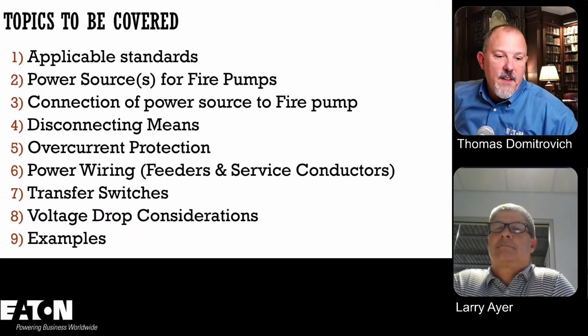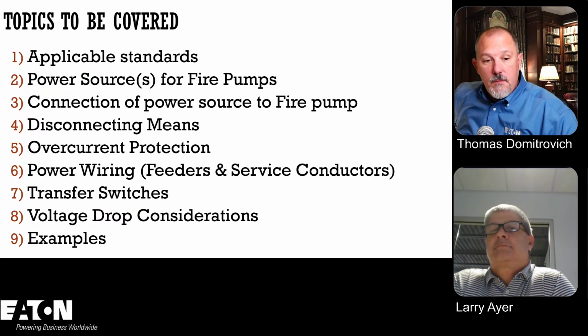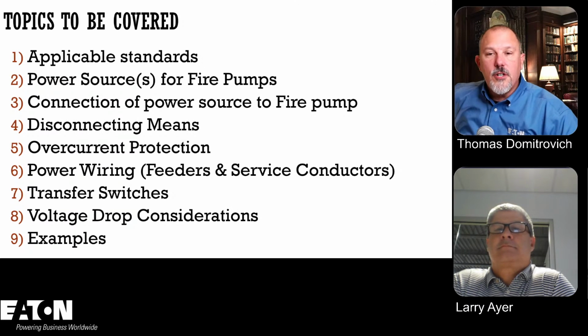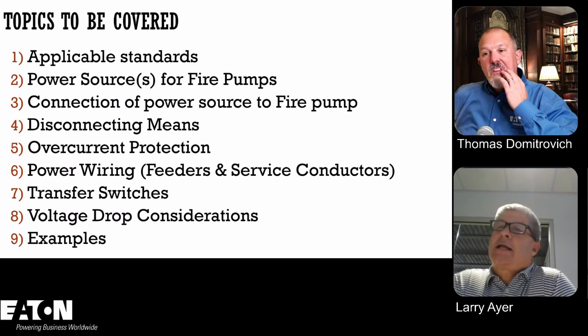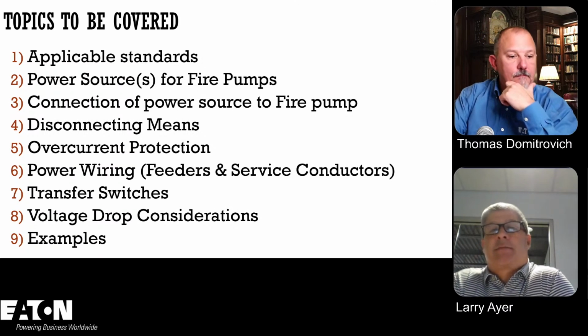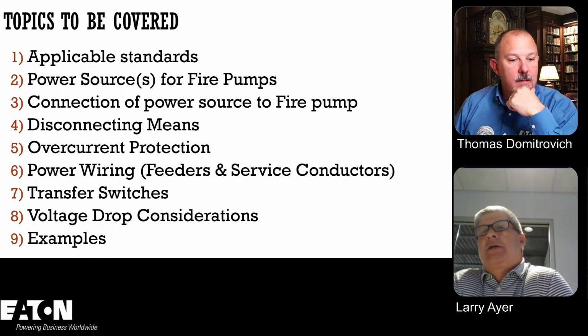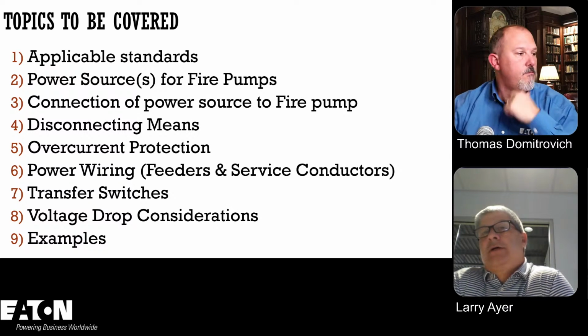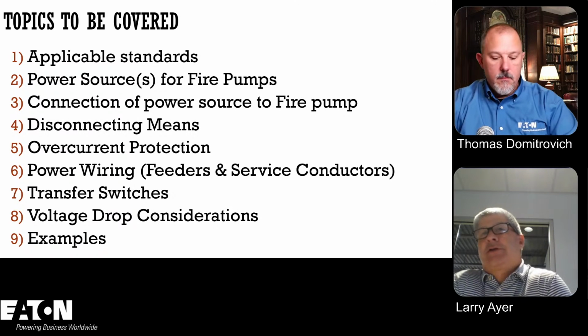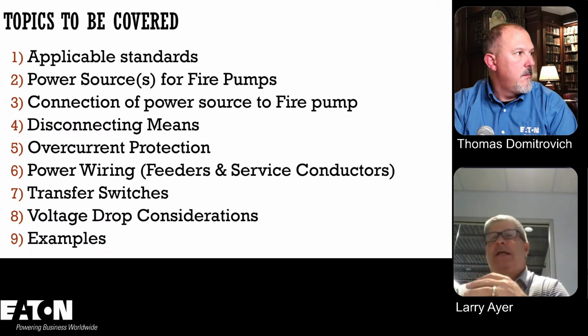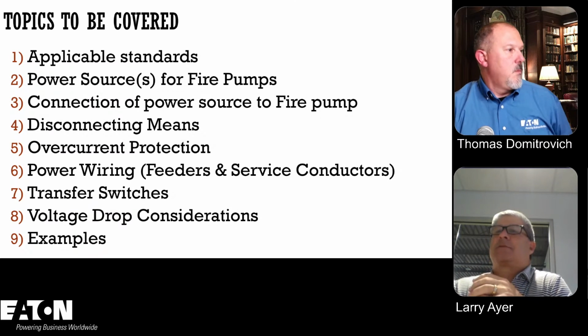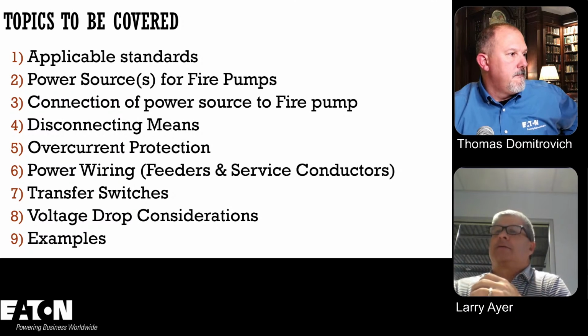He says they've moved away from tapping the fire pump circuit since it is very hard to comply with the tap rules. Good point. The fire pump overcurrent protective device is 6 times the current or equal to locked rotor current. Yeah, and I don't see many tapping the conductor. Like Mather says, let's say you have a 200 amp feeder for a fire pump, and then you're trying to feed maybe a 20 amp circuit to a jockey pump. There is that code rule. You can do a 10-foot or 25-foot tap rule and things like that, but it is kind of difficult, and it's much easier just to feed it with a branch circuit from somewhere else.